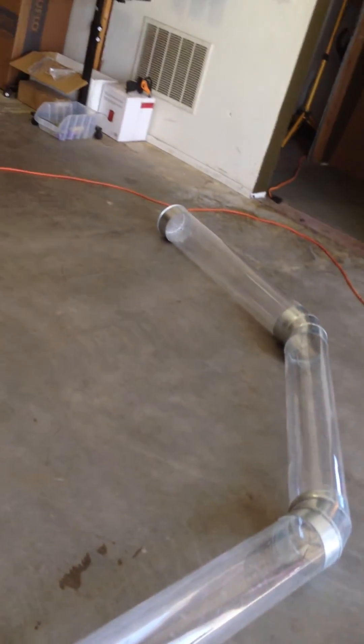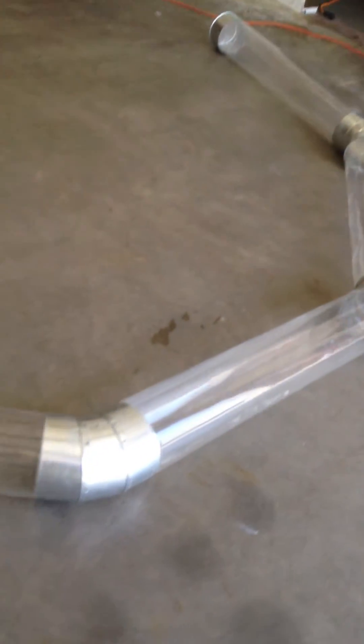In fact, it's actually overcoating at this point. The first couple of feet is getting absolutely drenched, and absolutely nothing is getting on the walls of the duct past that. So all that remaining ducting is getting absolutely nothing.